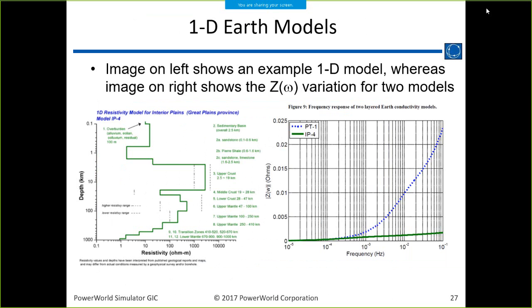If you look at an Earth model for one of the regions, this is what the conductivity of the Earth is going down from 100 meters, a kilometer, 10 kilometers, 100 kilometers, 1,000 kilometers. It gets more uncertain as we go down further. We might know what it is within the first kilometer down, but when you start getting down 100 kilometers, these are the error bars on the assumptions there. That's a log scale, so they think it's between this value, but maybe a factor of 100.